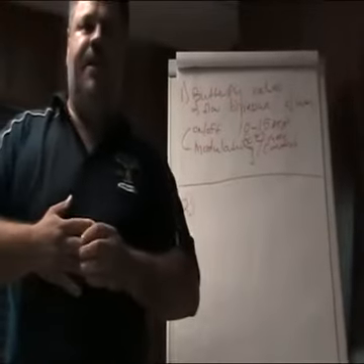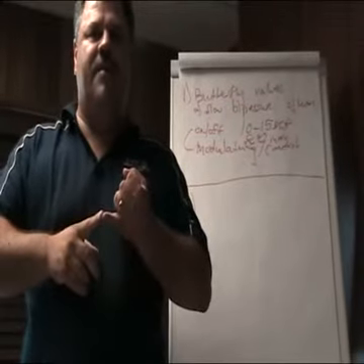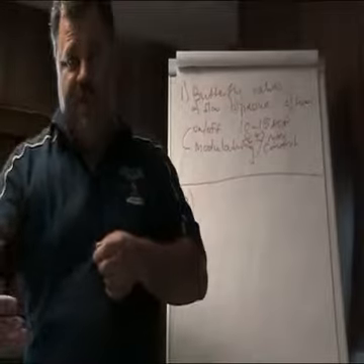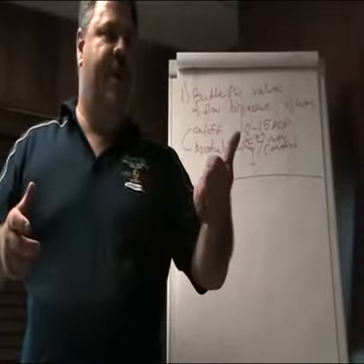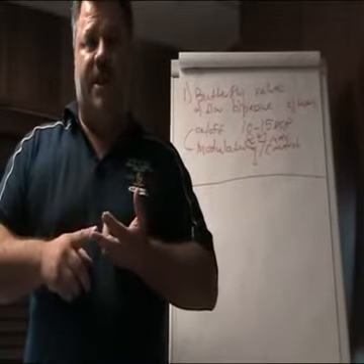But okay, so on the high performance butterflies, high performance says a lot. It means high temperatures, high pressures. Where this little low pressure valve can handle only 200 maximum, or 80 we said, but if you put PTFE in, 200, these high performance disc valves, whether it's double, triple or centric, can handle temperatures up to 500 degrees Celsius.